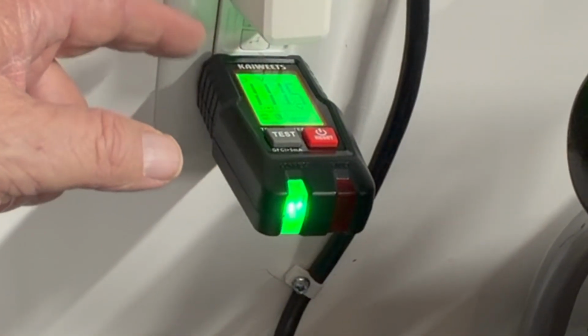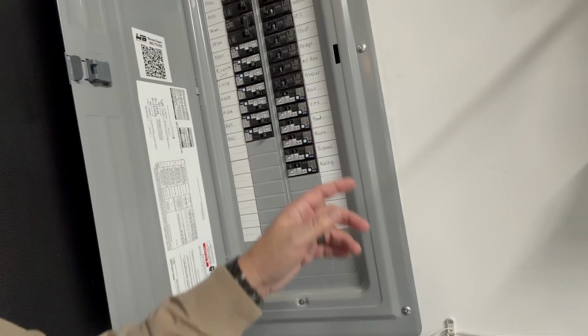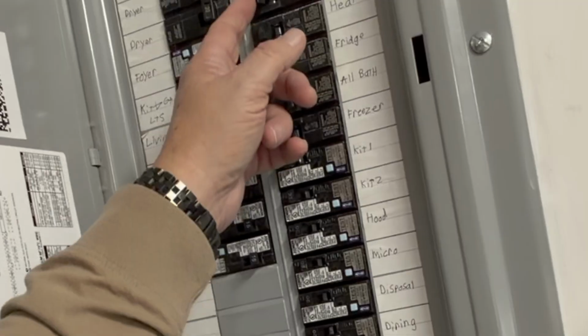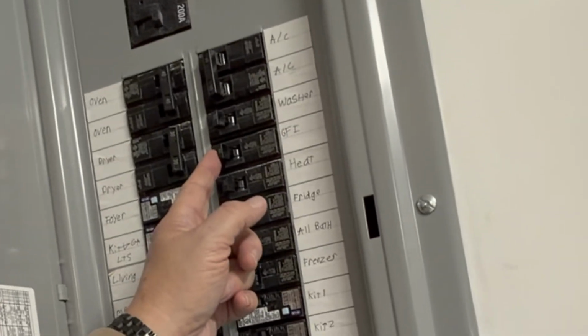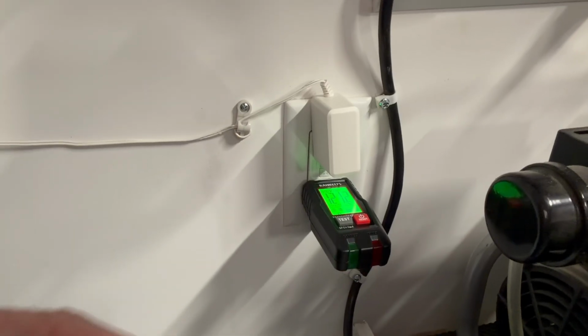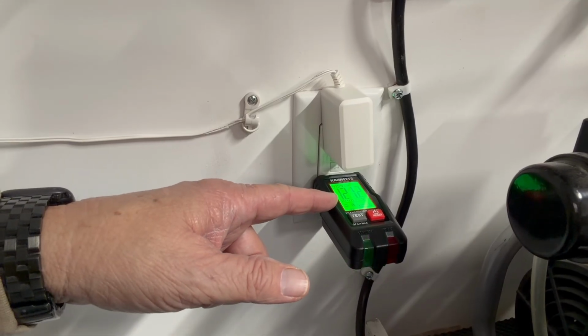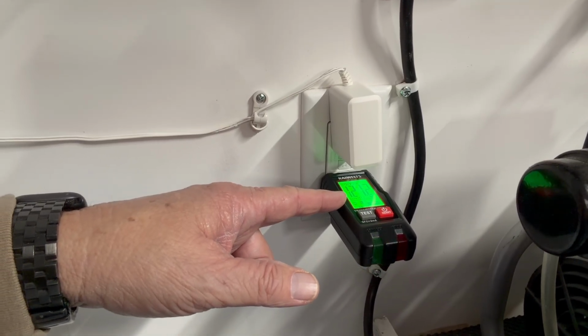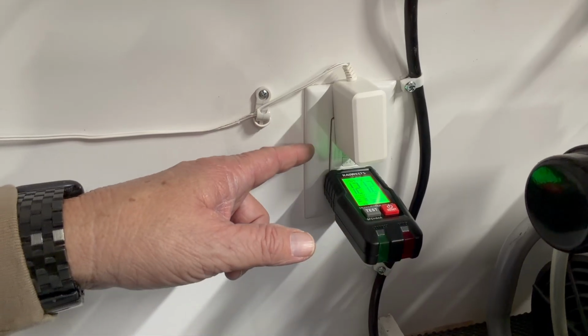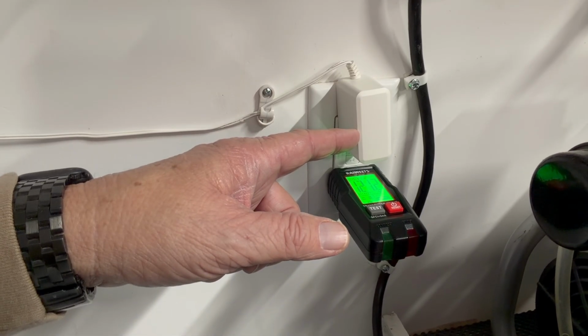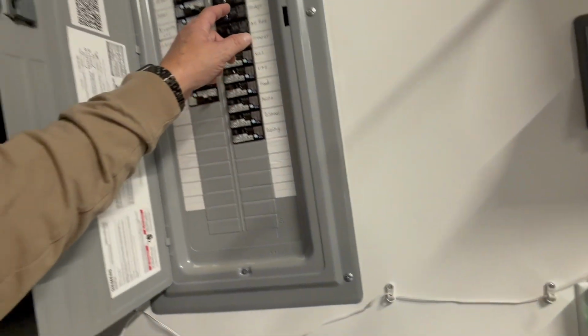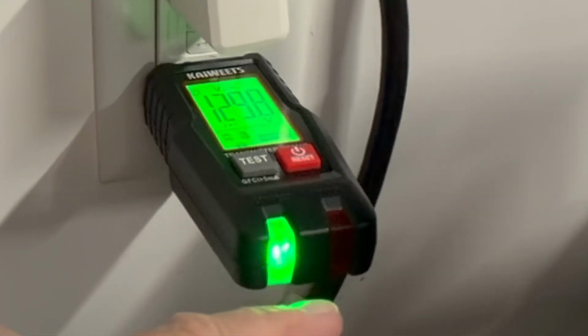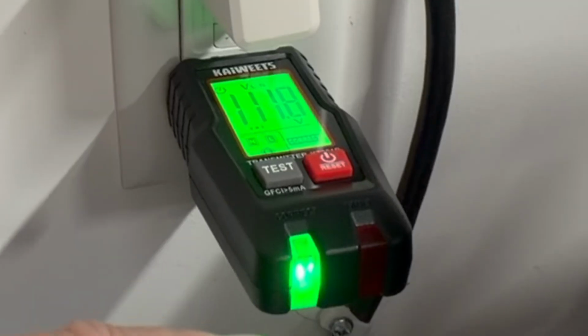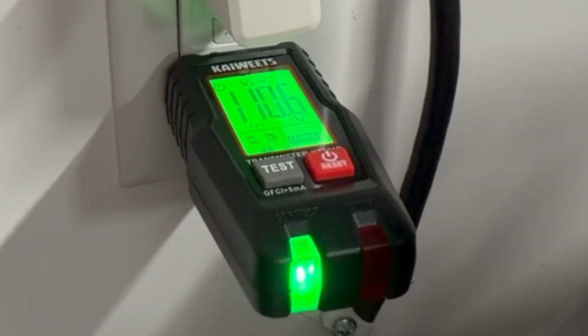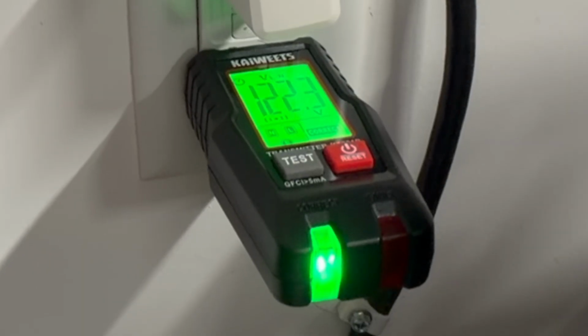There are no faults in the ground wires and so forth, and polarity. Now you can test this ground fault plug by breaking it there, or another way, we can close this known circuit off right here. We can turn off the circuit. Now if you look at the light, it's blinking. Still showing 121 volts of what was initially applied to it, but there's no electricity flowing through this plug, so my internet is actually down now. As soon as I turn the breaker back on, you can see the light is now solid green, indicating there's live voltage from this particular outlet.